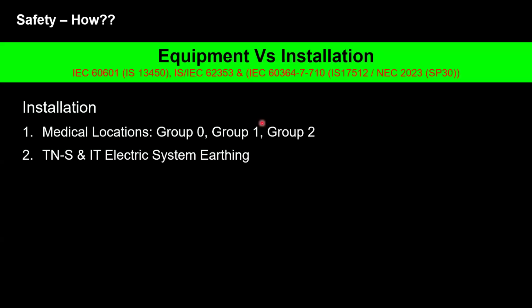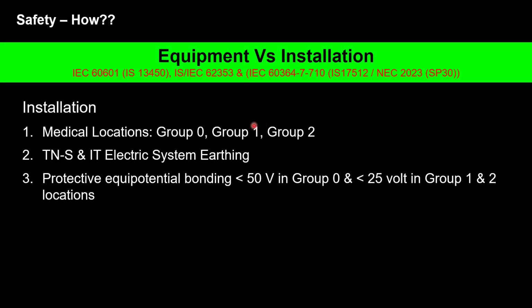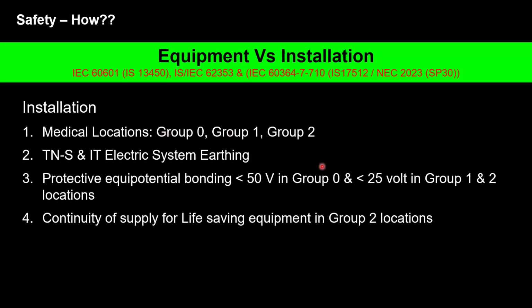So basically, the additional safety measures required are medical location classification, the type of system earthing, the type of equipotential bonding. Basically, additional bondings are required within the group 1 and group 2 medical locations. Continuity of supply, electromagnetic interference. So there are several measures. These serial numbers 1 to 5 are not the entire list, but this is an example of some of the safety measures required in the medical location. So very critical. Now, what happens actually?